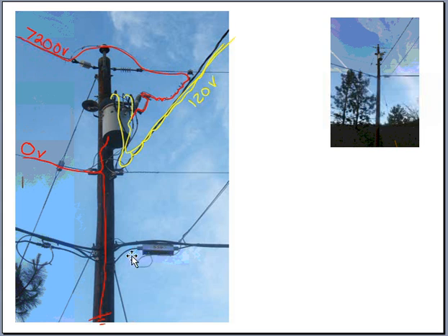And they're down here so that the telecommunication workers can just climb up to there and make their adjustments. And then farther up the pole, we put the more dangerous voltages where you're actually distributing some power. So on this power line, this is actually out in Naramata, you've got 0 volts on this wire. It's actually connected to ground with a little wire that runs down the pole and literally goes into a stake into the ground. And then the feeding voltage here is 7,200, and it goes in, so I've drawn that in red, it goes into this transformer.